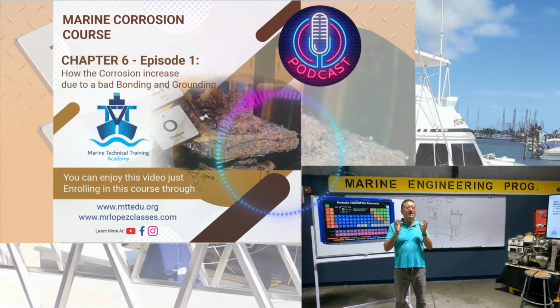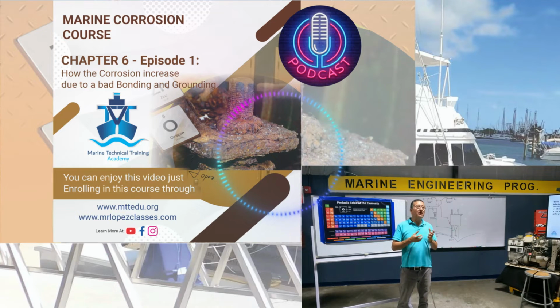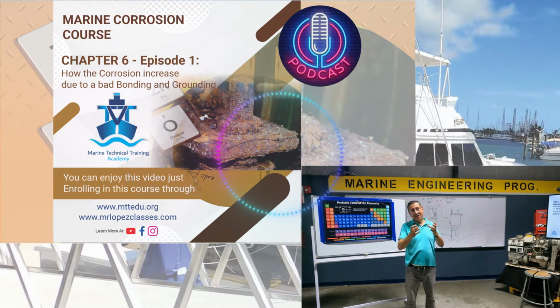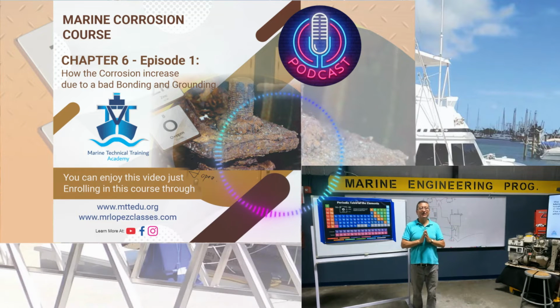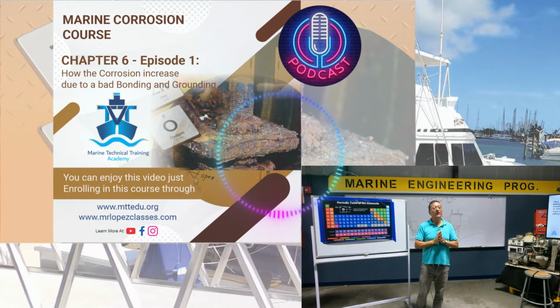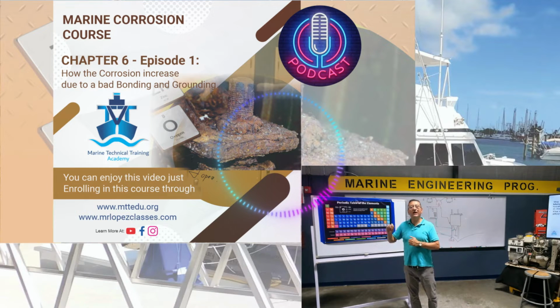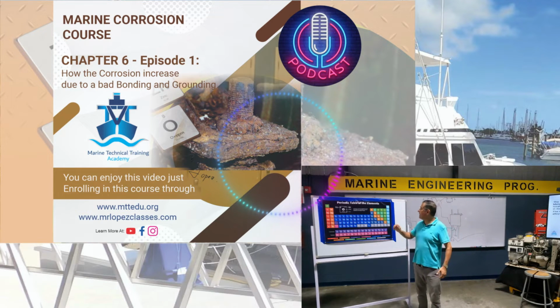Grounding is when you connect that bonding conductor externally with the zinc on the transom, the zinc that you have on the screen right now. That connection between the bonding and the external zinc, this is grounding. And ground is the reference to the ground. It's the direct connection to the ground. Is that clear? Bonding is the internal connection of all the metallic parts to the bonding conductor. And grounding is the connection between the bonding conductor and the external zincs. Alright.